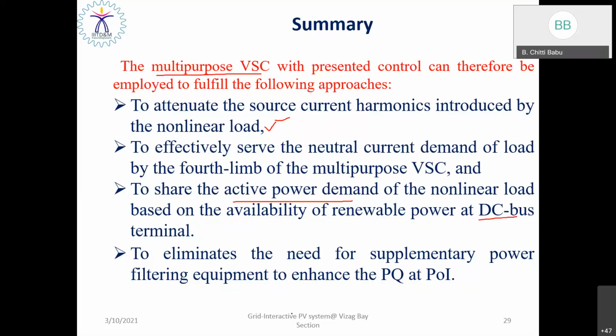And there is a strong supplementary power filtering function, as the voltage source inverter with a suitable controller can also act as an active power filter to mitigate harmonics in the grid current due to the introduction of non-linear load at the point of interconnection. These are the main objectives, so that by satisfying the grid connection requirements, we are able to interface the solar PV system with the utility grid.